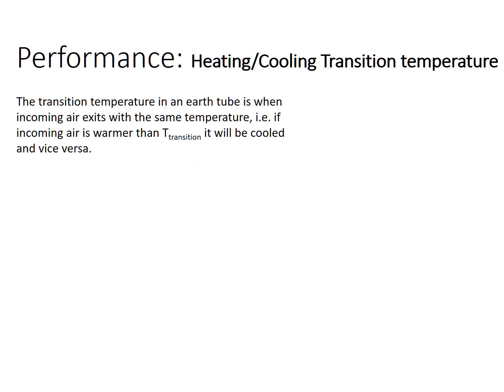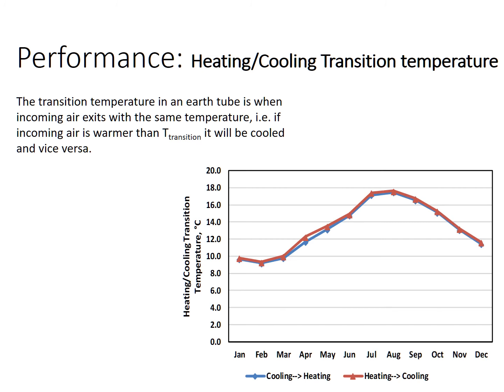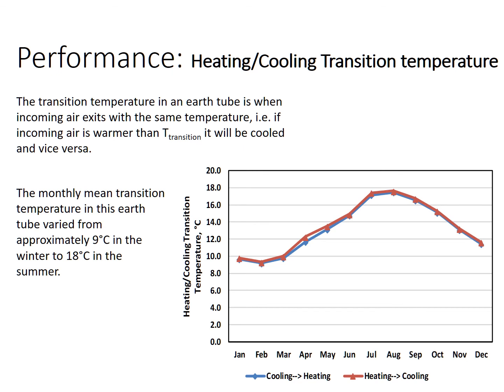So we can look at that by looking at the transition temperature, which is when the air coming into the earth tube exits with the same temperature. And if it's any warmer, it'll be cooled, and if it's any cooler, it'll be heated. That's the transition temperature. This looks at the 6 years data, monthly, January to December again here, and we see the incoming transition temperature here goes from in the winter, January, February, around about 9 degrees up to 18 degrees almost here. So there's a very big difference in the temperature there, which is responsible for a lot of that scatter.